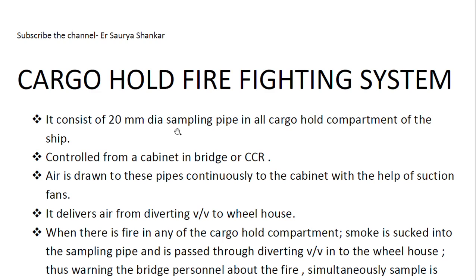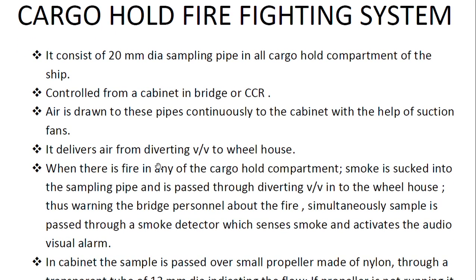The system consists of a 20 mm diameter sampling pipe in all cargo hold compartments of the ship. This is important — a 20 mm dia sampling pipe goes to all cargo hold compartments. This system is controlled from a cabinet on the bridge or CCR (Cargo Control Room). Air is drawn through these pipes continuously to the cabinet with the help of suction fans — similar to the Oil Mist Detector (OMD). Samples are drawn from different cargo hold compartments using the suction fan.